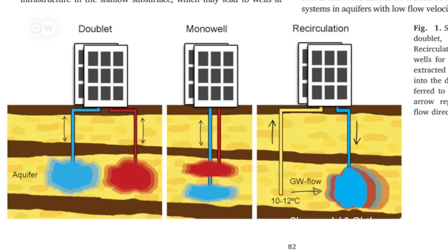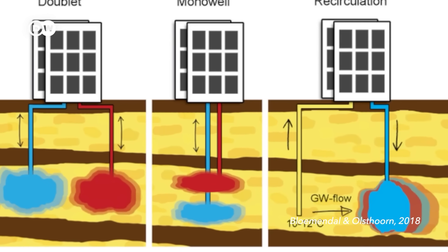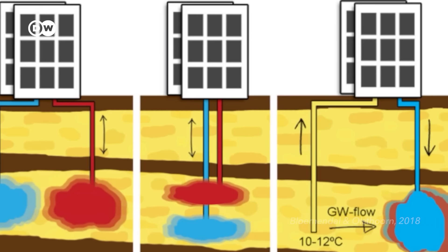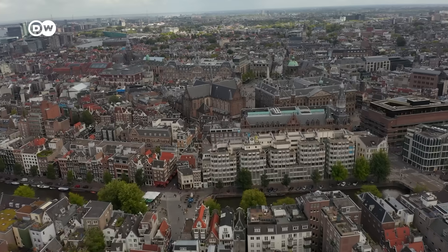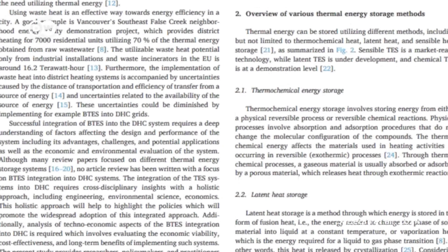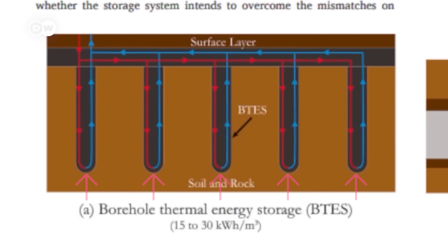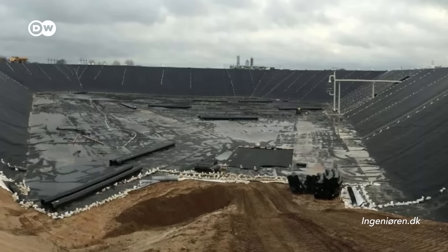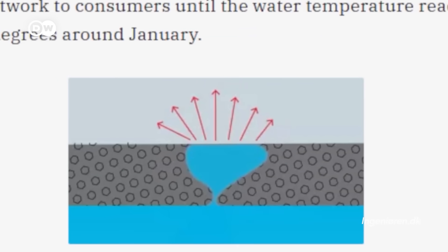Places with less solid bedrock have to store heat differently. You can heat up natural underground layers of fractured rock, sand or gravel that hold groundwater, which you access by drilling wells — that's being done in many places in the Netherlands and also in Germany. Its parliament building is heated this way. Another technique is to make boreholes up to several hundred meters deep, through which a hot fluid is circulated, heating up the surrounding rock, soil or clay that then stores the heat. Or it's possible to dig a huge pit, line it with waterproof material and use it to store hot water, like in Denmark.